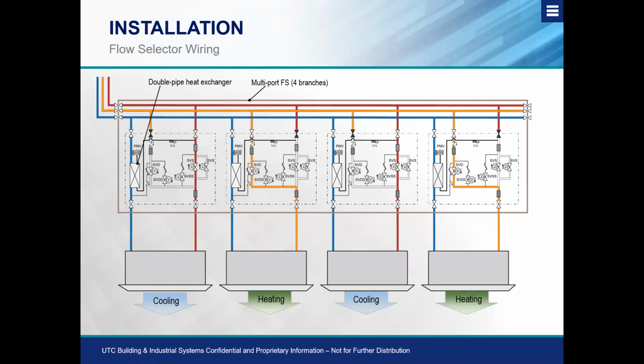We're able to control that refrigerant flow and also use byproducts of particular areas. Basically, for areas that need cooling, we're taking their hot air and giving it to somebody that needs heat. Now, if all of these are calling for the same mode and we don't need to recover anything, we're just going to take that unwanted heat and discharge it in the atmosphere like we typically would with a system that is running in cooling, and vice versa in heat.